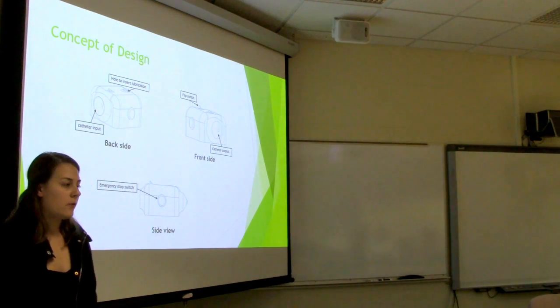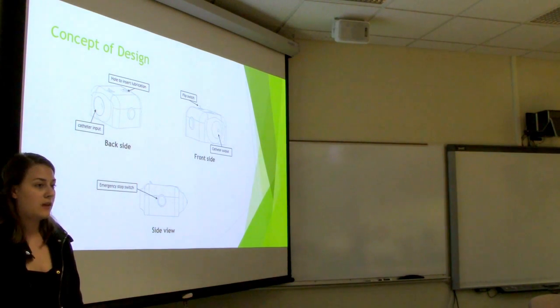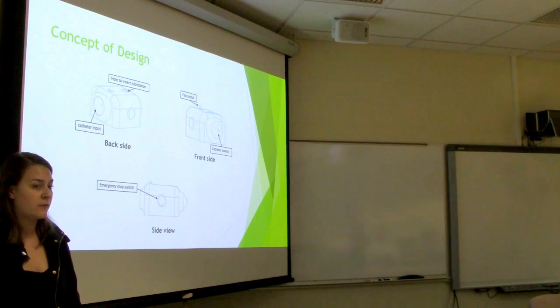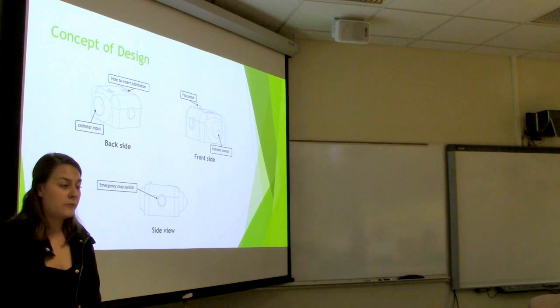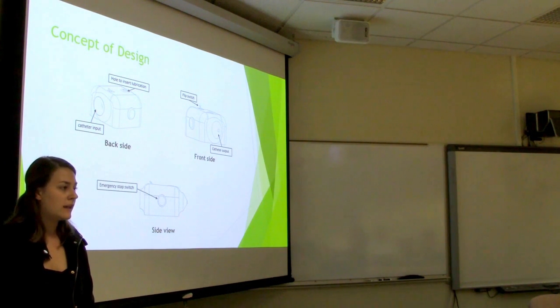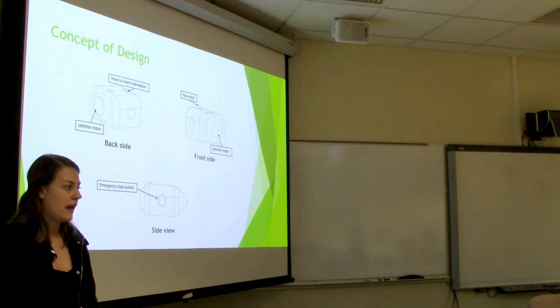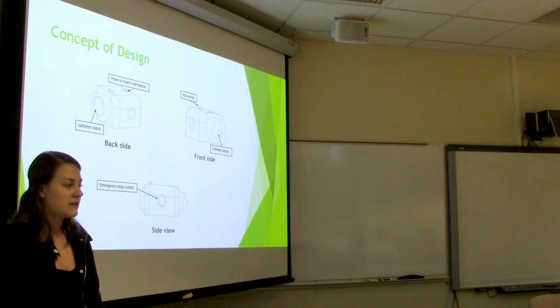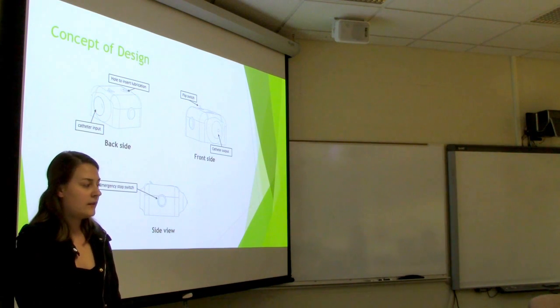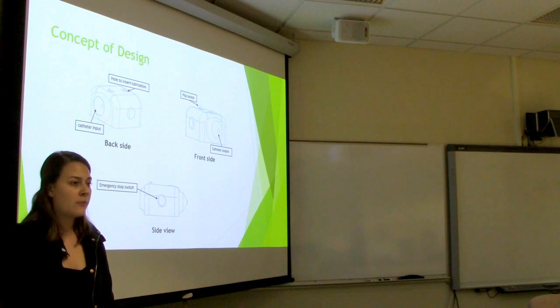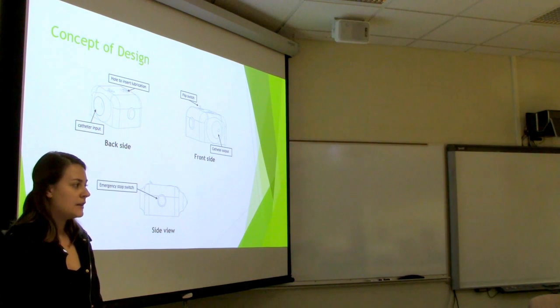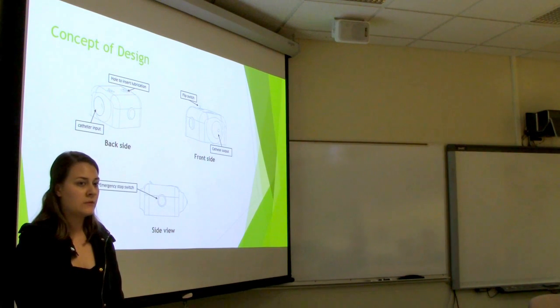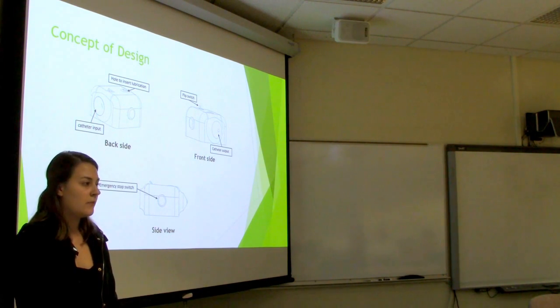I also created a brief sketch of what the final product might look like. This is by no means a final product, but highlights a few important features that need to be considered for the final design. On the back side, we see the catheter input into the device. And this is going to be a funnel-like shape. Somebody with tremors is going to have a very hard time inserting the catheter into a small opening. So this funnel provides a guide so that involuntary motion can still happen, but the catheter moves into the device easily and smoothly. The hole for lubrication on top of the device is also built in this funnel-like design for the same purpose. On the front side, we see the catheter output and the flip switch to control the device. And the shape of the catheter output can be better seen on the side view. It's tapered down almost like the end of a funnel. And this would allow the individual to line up the device with the urethra to allow a smooth transition from the device into the body.